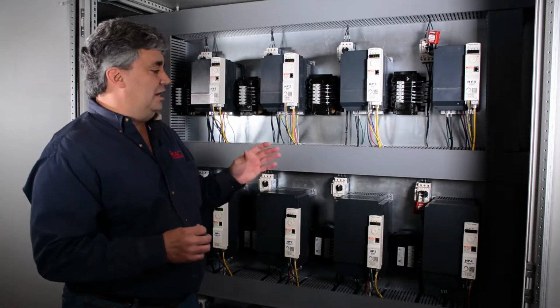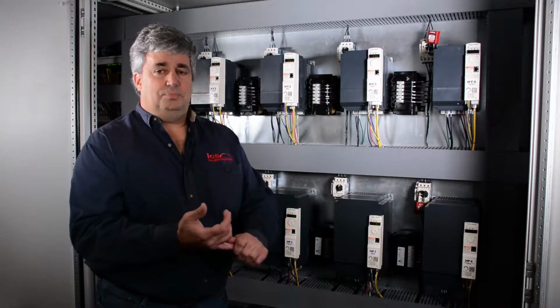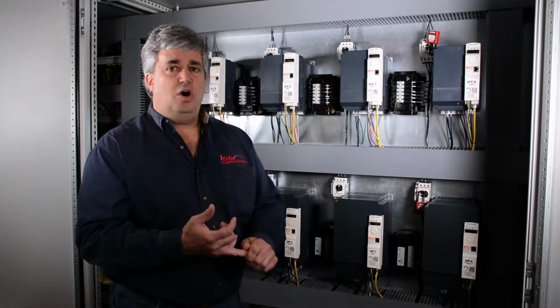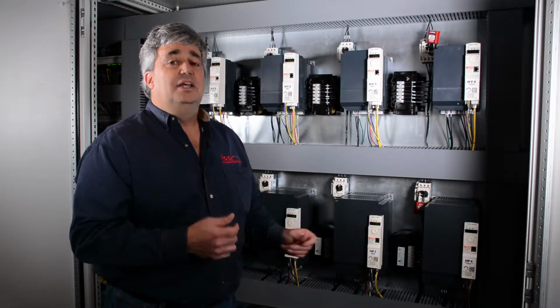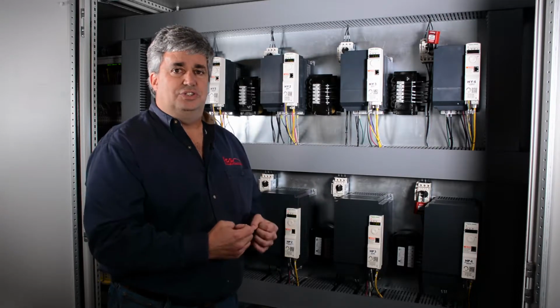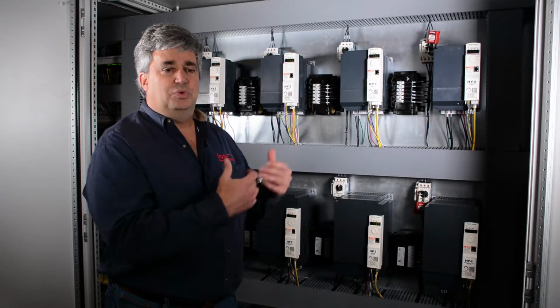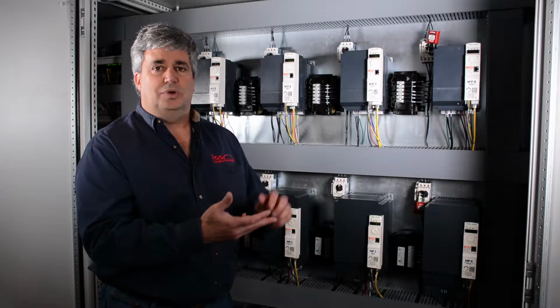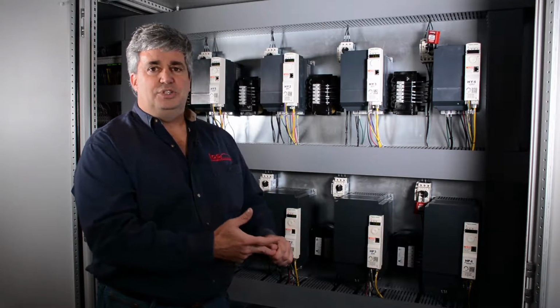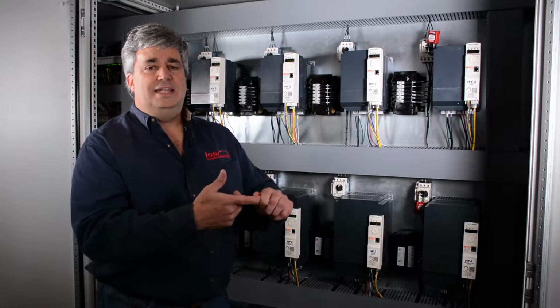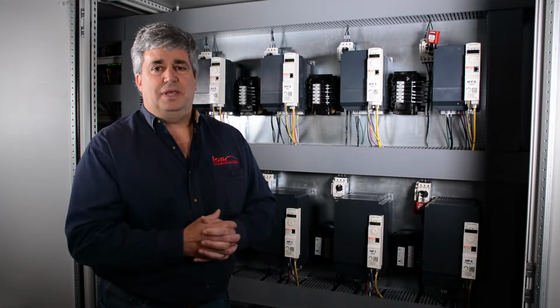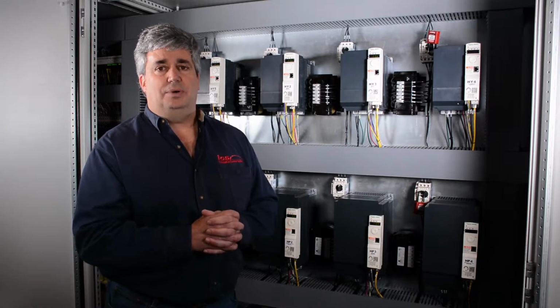So when you look at a high pressure pump, we're looking at the pressure transducer and low water coming back to the VFD. The HMI reads the status of those inputs to know that the drive is working correctly, that there's enough water, we're at the right pressure, the RPM is correct for the pressure we want, and the amperage is correct for the RPMs we're running and the load on the pump.